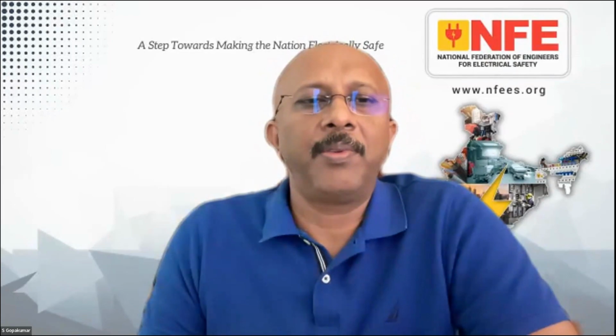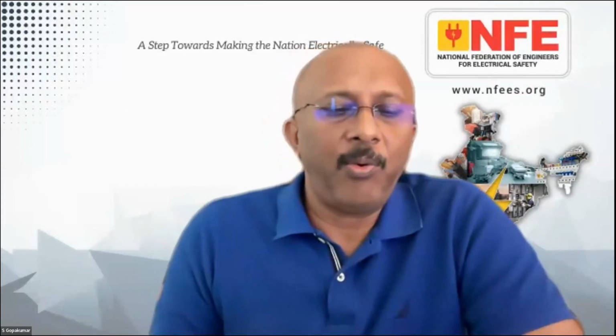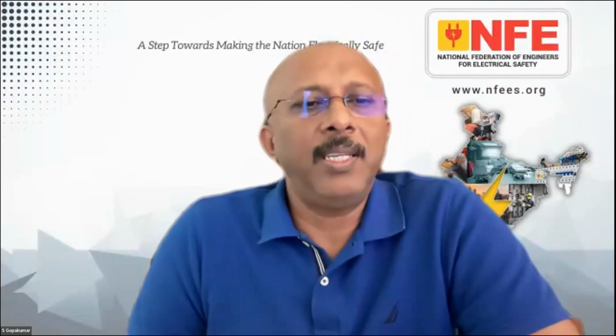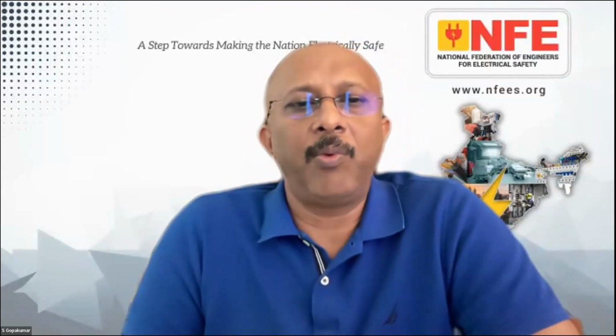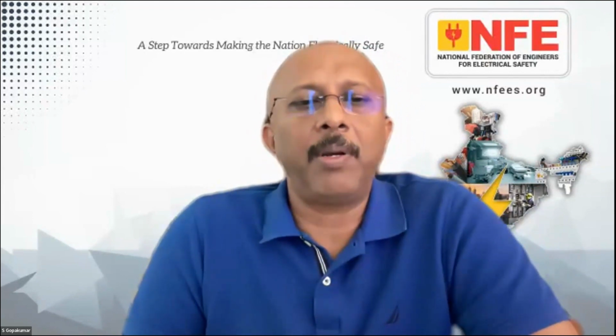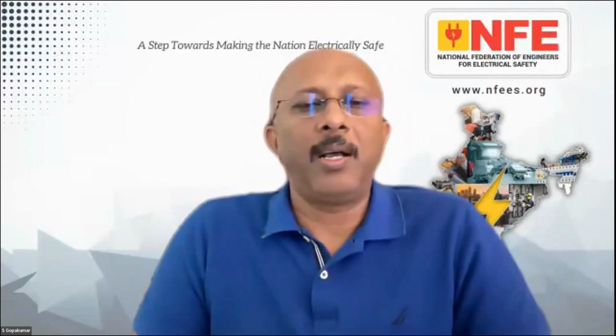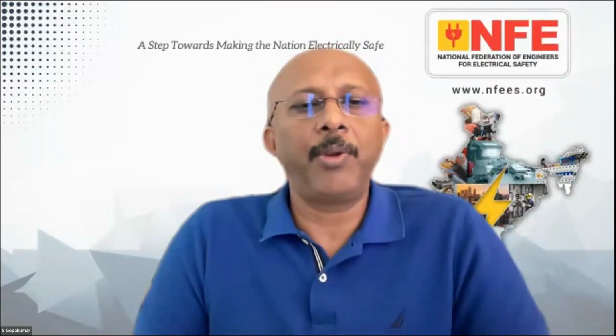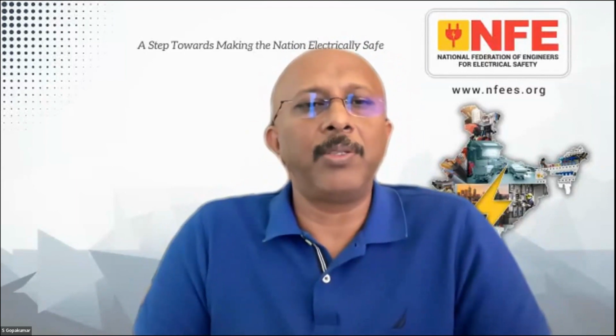Yeah. Well, pretty much, the standard part that we are referring to here is on low voltage electrical installations. Actually, here our situation is a little bit different. In cities, for example, the voltage drop is probably within the limit. But if we go to rural areas, the DISCOM says my line to neutral and line to earth voltage is, for example, 230 volt, but in actual we may get only 150.